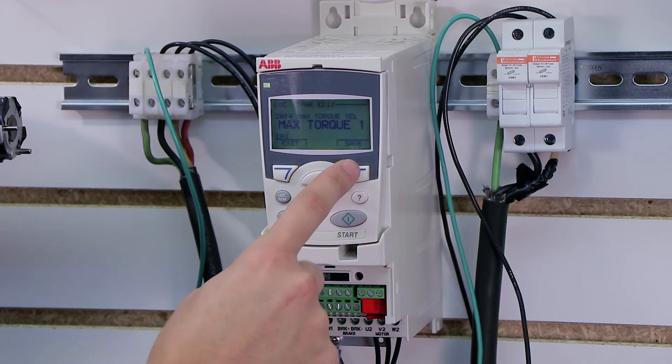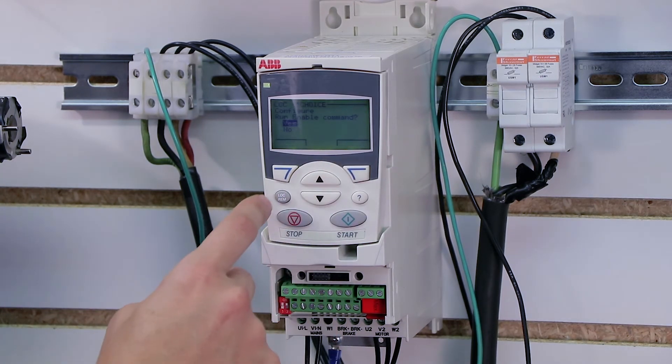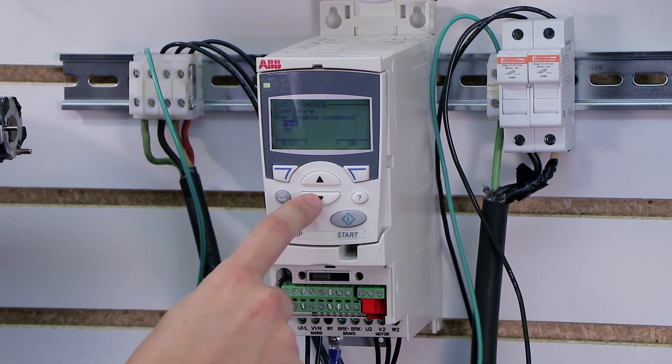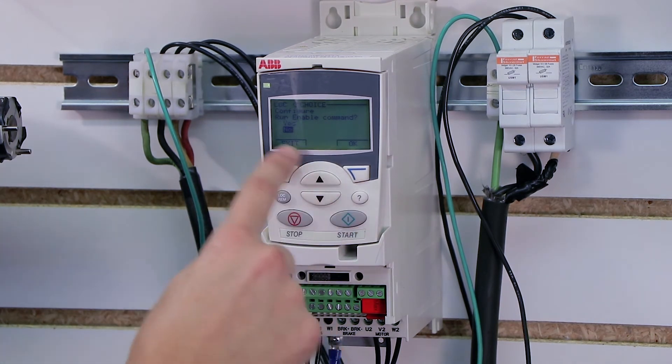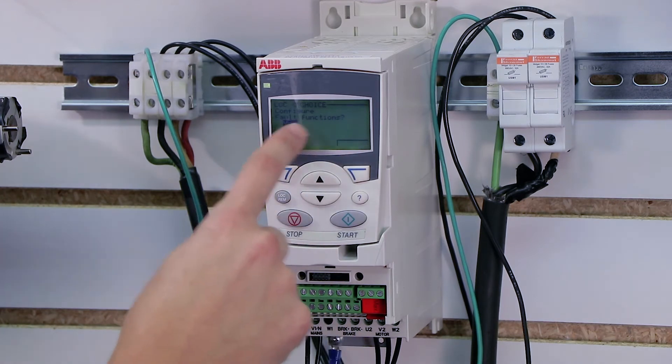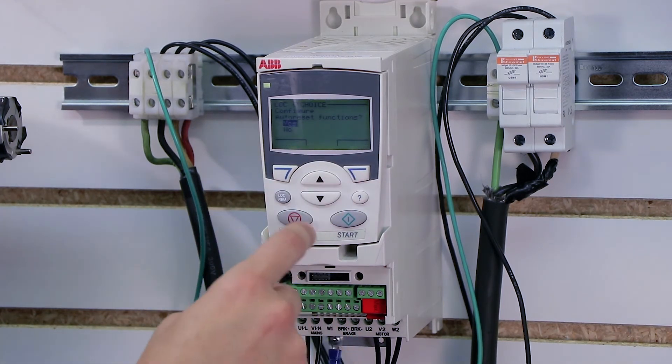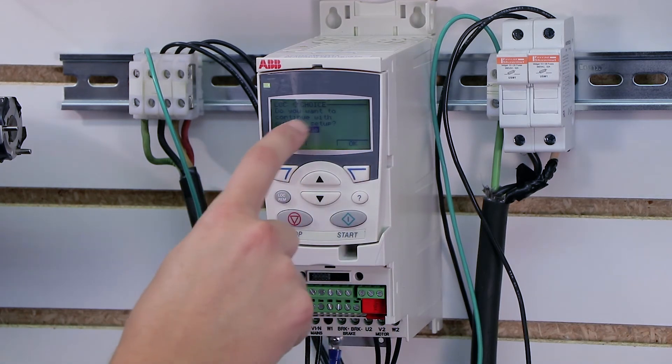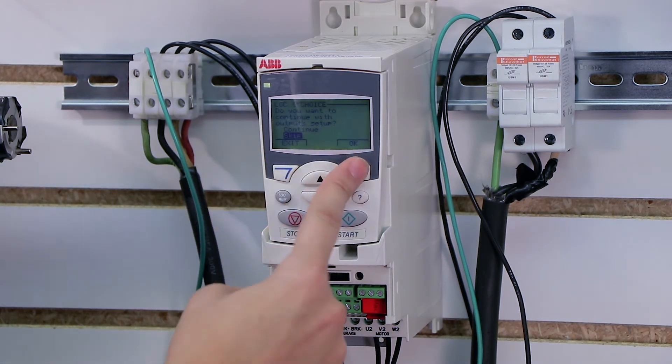Max torque, we'll just leave the default. And then it asks me if I want to configure the run enable command. This is a command that's built into the drive to require like a jumper. I'm going to click no. Do I want to configure the fault functions? No. Do I want to configure the auto reset functions? No. Do I want to continue with output setup? No. Skip.